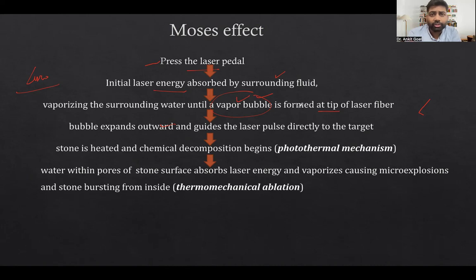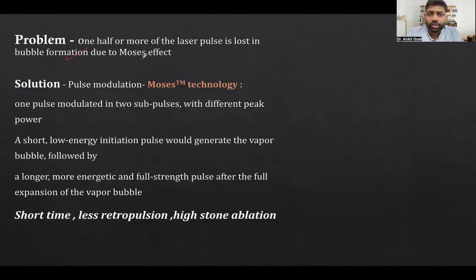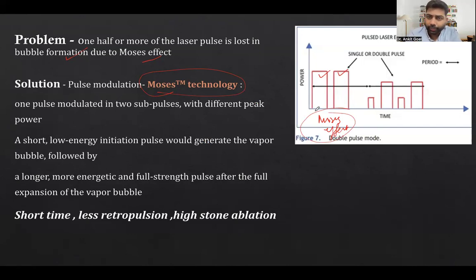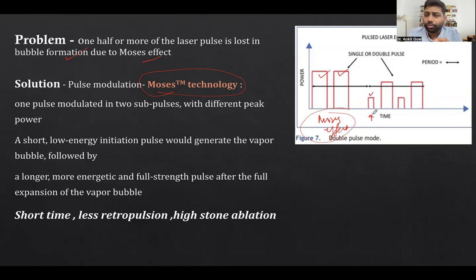The solution to the Moses effect is Moses technology, which works by the principle of pulse modulation. With a single pulse, only half of the energy reaches the stone — the rest is wasted creating the water bubble path. Moses technology addresses this by first delivering a small low-energy initiation pulse that generates the water vapor bubble and creates the path to the stone, so that by the time you generate the second pulse — a longer, more energetic, full-strength pulse — it can be transmitted efficiently.